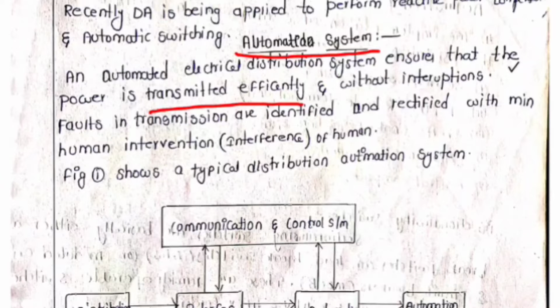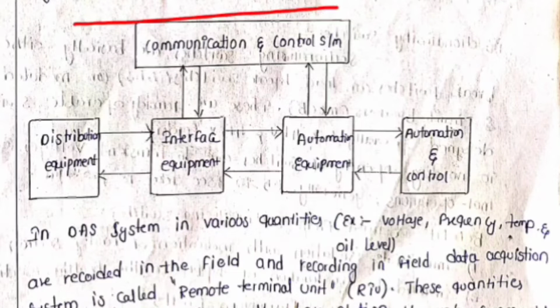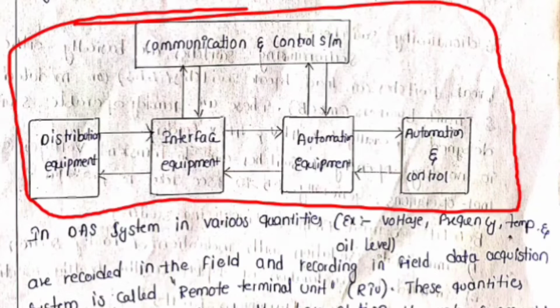The basic figure shows a typical distribution automated system. It consists of a communication and control system, that is, a computer. The distribution equipment is interfaced to the communication port using an RTU, the interface equipment, or SCADA, and many other automation and control equipment. This is a block diagram of the communication and control system. In the distribution equipment we use normally open and normally closed switches, relays, CTs and PTs.